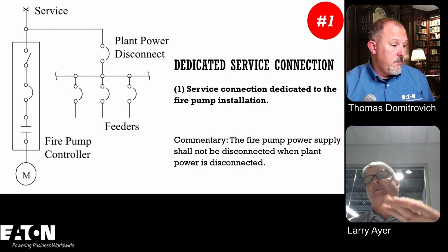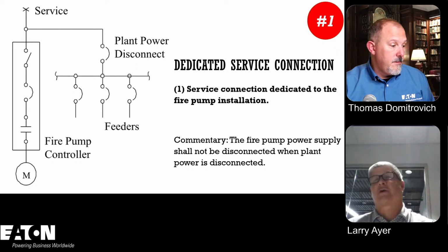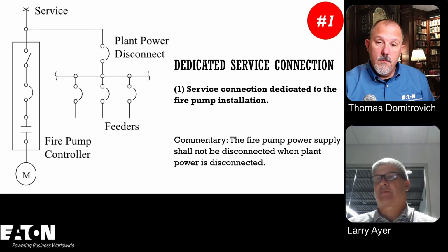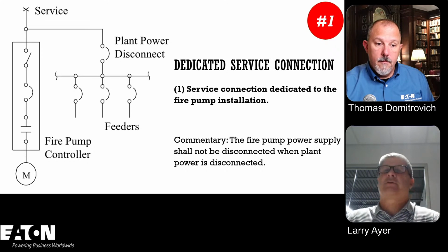Also, some people get confused because when you have services and you have a fire pump that only needs 3 wires and you tap off that service to go to the fire pump, at the first means of disconnect you have to bring that neutral there, whether you use it or not, even though it's a 3-wire fire pump. So sometimes people get confused on that, and you've got to think of those things.